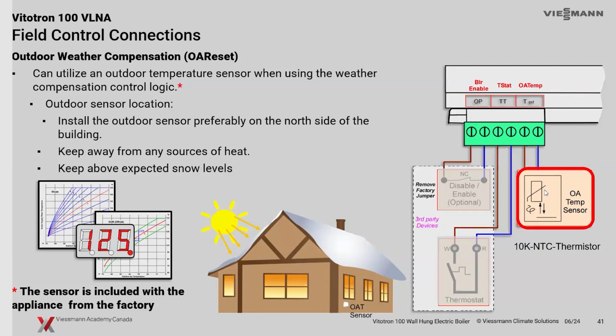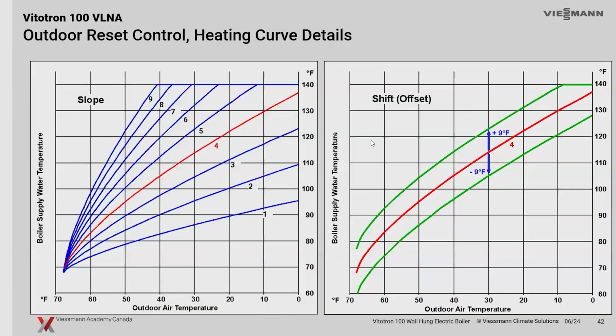To utilize the outdoor reset function here, if you don't want to use it, you can also use what we call constant supply temperature. You can program in a fixed temperature, so it'll operate either way for your space heating system. When you do that, you'll notice on the display screen there's a little red dot at the very bottom right-hand corner. When you're using outdoor reset, that little dot is illuminated. When it isn't, you're in fixed set point operation. And there's the heating curve that we're looking at.